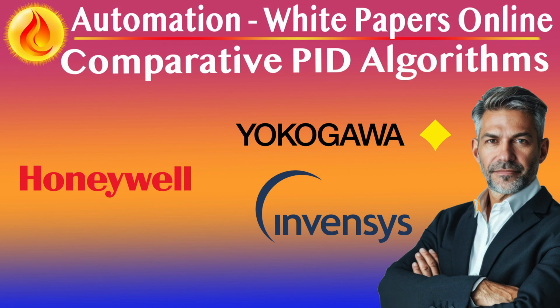In contrast, Yokogawa handles cascade and feed-forward logic through external function blocks. While this provides maximum architecture flexibility, it requires the engineer to design mode tracking logic, biasing, and override behavior manually. This is powerful in specialty plants with custom blending, adaptive logic, or constraint-based overrides, but requires deeper control design expertise.